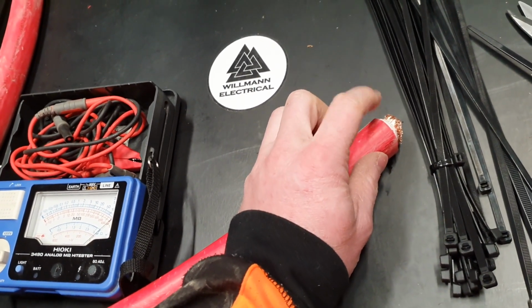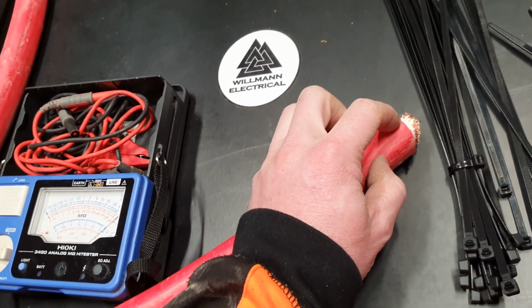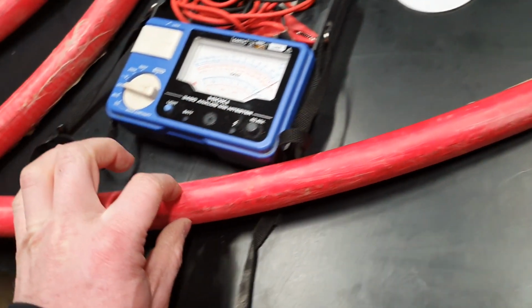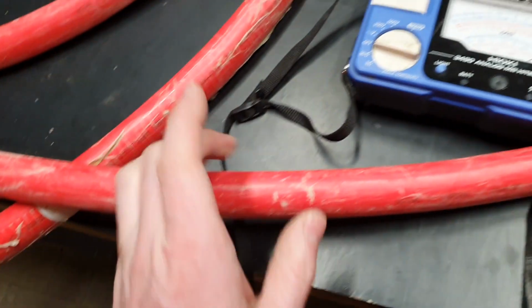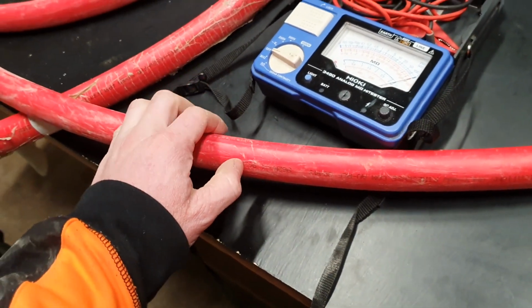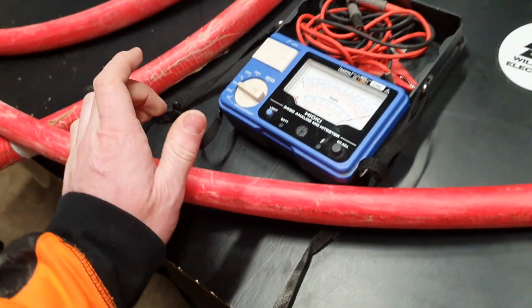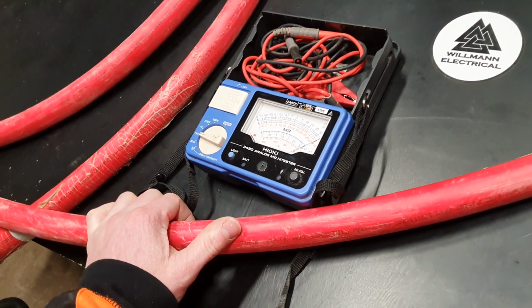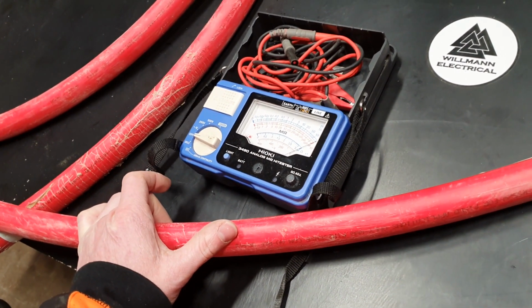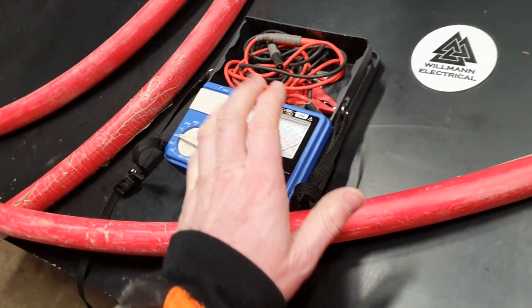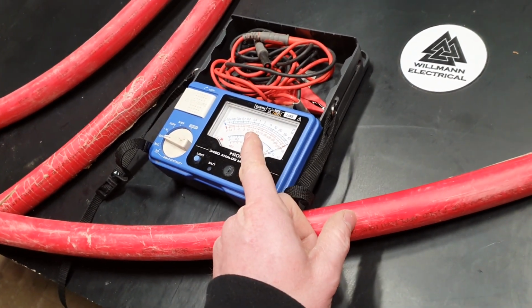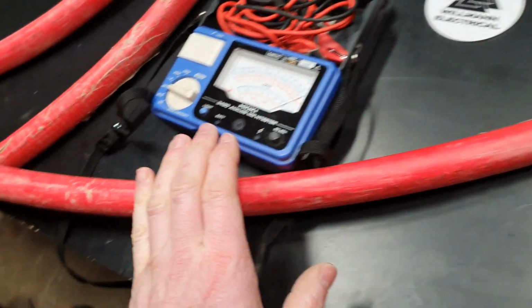I'm going to hook this end up to the mega and just wander along the cable to see if I can find a pinprick or something in this cable. This part was probably in the dirt, potentially wet. So I'm just going to wander along, whack it on 1,000 volts, and see if I can find anywhere on this cable that's getting a little dip in the reading.